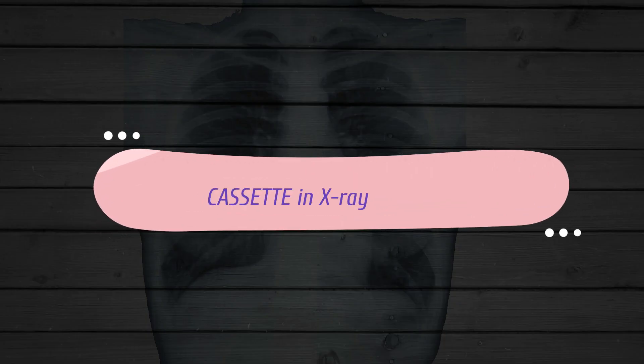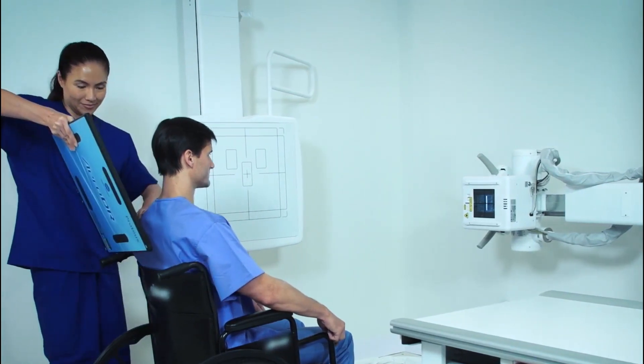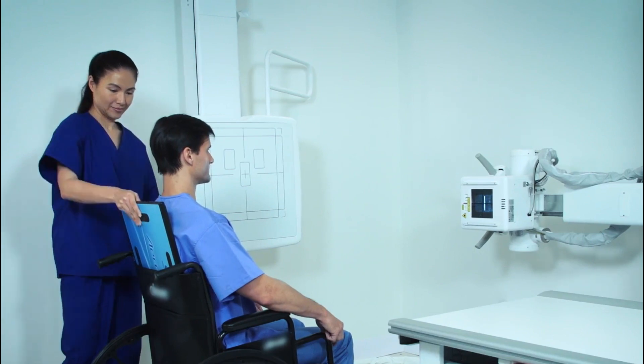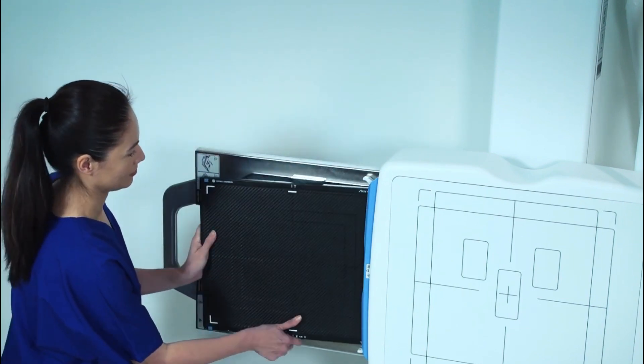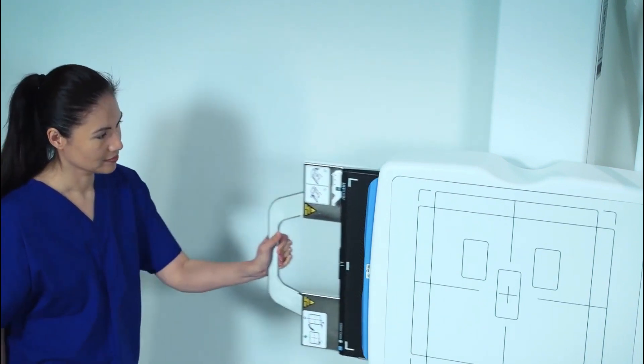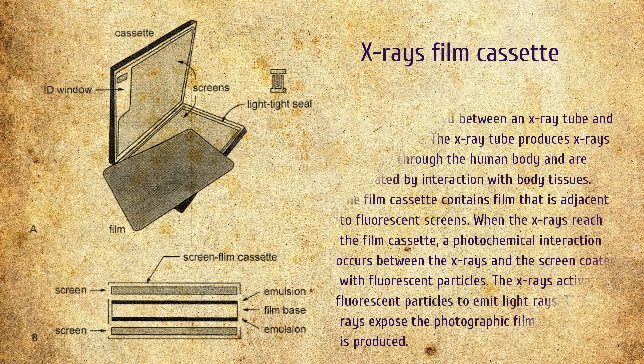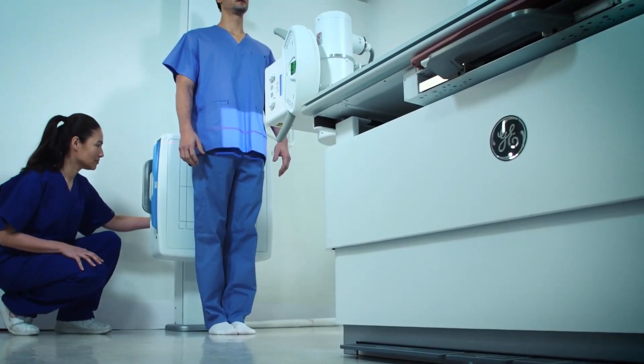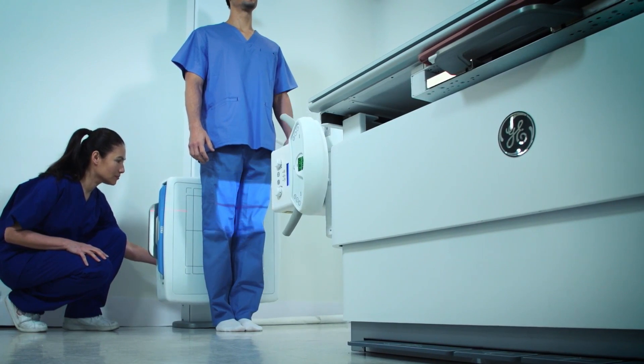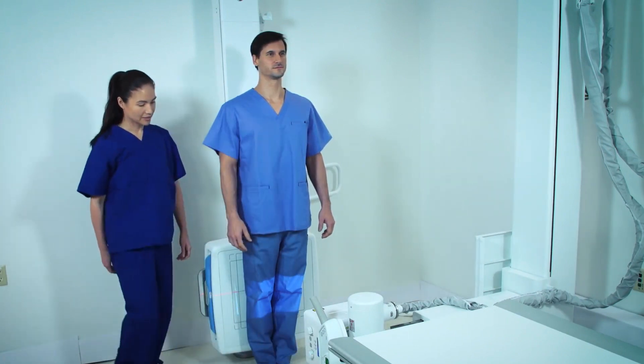Let's look into the cassette in x-ray machines. A cassette is a flat, light-tight container in which x-ray films are placed for exposure to ionizing radiation, and usually backed by lead to eliminate the effects of backscatter radiation. The structure of a standard cassette resembles a book, consisting of two flat rectangular plates hinged along one edge. The front aspect faces the x-ray tube and consists of a sturdy metal frame into which is fixed a sheet of either light metal such as aluminum or plastic material — the critical point being that it must be transparent to x-rays. The frame constitutes a shallow container into which can be placed a thin intensifying screen and film. The back of the cassette is constructed from a strong metal, and it is customary to spray the internal surface of the back with lead paint to absorb secondary radiation scattered back onto the film.